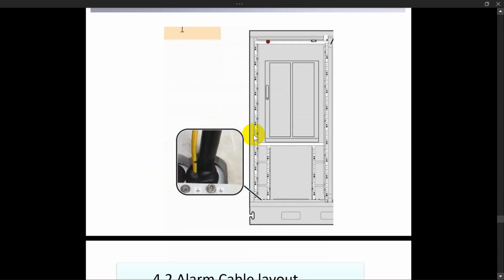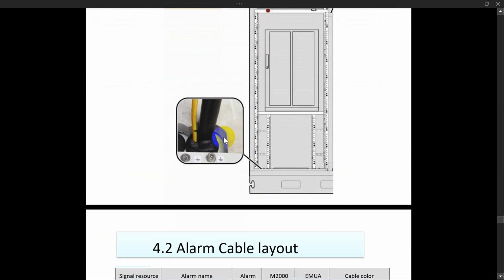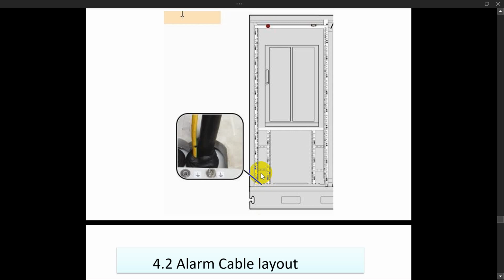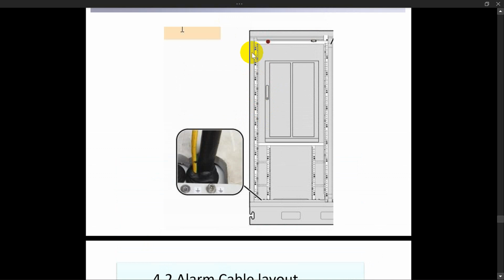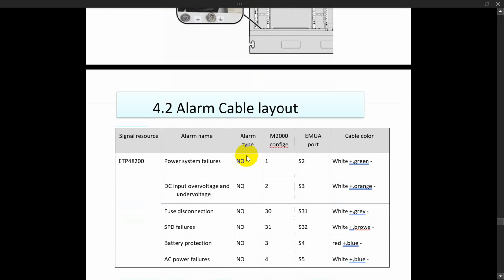This picture shows one mini shelter with a 19-inch rack, how he connects the rectifier and DCDU, and on the upper side he puts the EMU, and down below he puts two strings of batteries. For the mini shelter, not like the normal shelter where the cable comes from up, here the cable is coming from the downside. So the cable will come from down and connect to all equipment upward. There is some type of outdoor cabinet where the feeder windows also come from the upside. So you can connect the feeder from the upside, and if you have other cables from down, you can use the down ports.